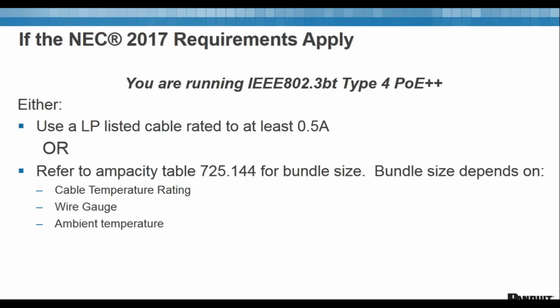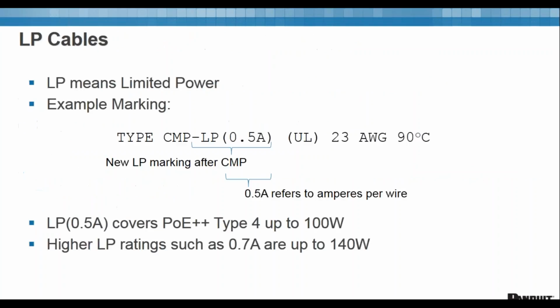Either you must use an LP listed cable rated to at least 0.5 amps, or you have to refer to an ampacity table for bundle size. And this bundle size given by the ampacity table will depend on cable temperature rating, wire gauge, and your ambient temperature. LP means limited power, and there's going to be a marking on the cable. This is a UL test all cable vendors would have to go through, and you would see it on the jacket.